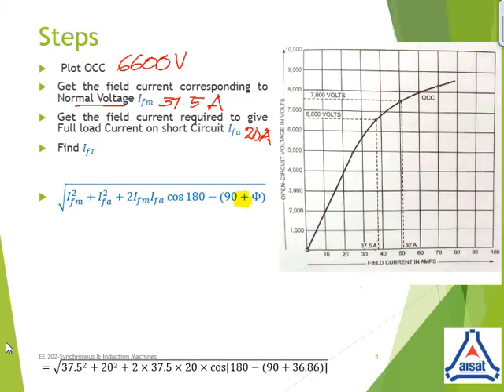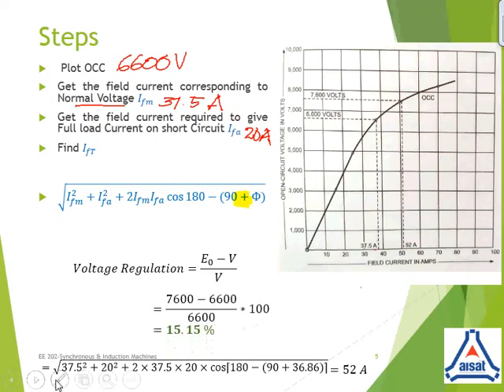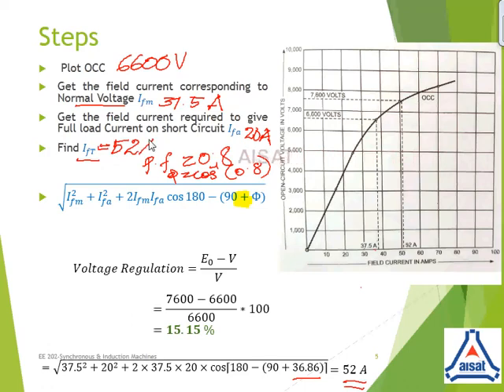How will you obtain the value of phi? Because in the question, it is given 0.8 power factor lagging. Which means that the power factor of the load is 0.8. Which means, phi is obtained as cos inverse of 0.8, which is nothing but 36.86. That's how this angle 36.86 comes. After computation, you will be getting a value of 52 amps. That makes your total IFT value. IFT value, you are now getting it as 52 amps.